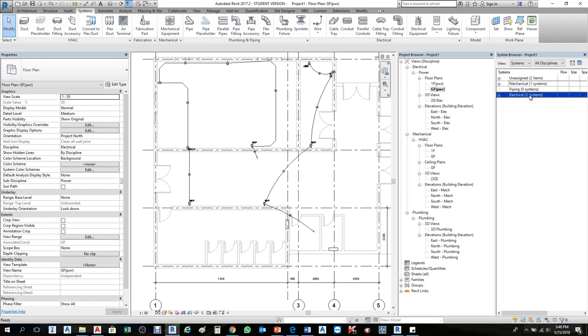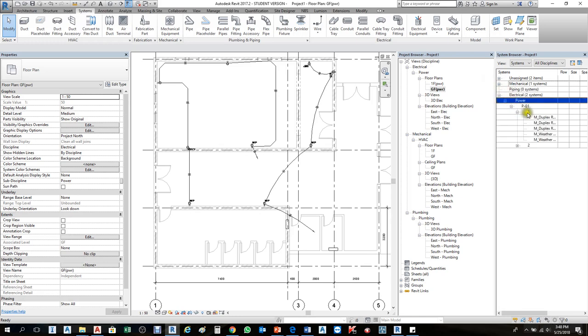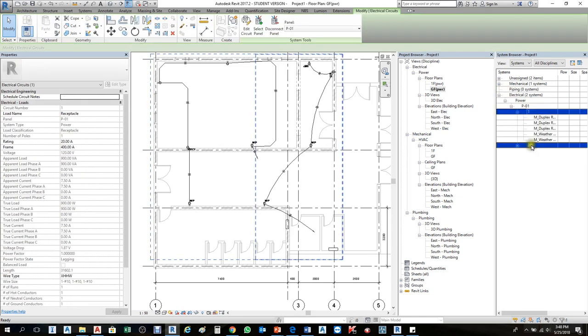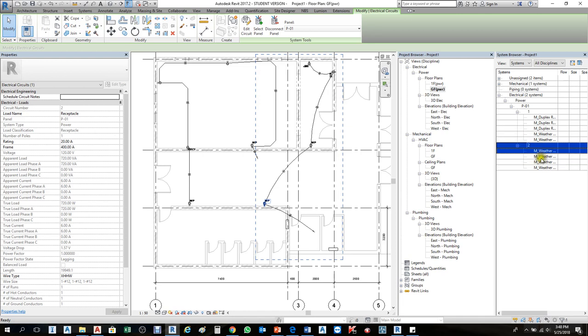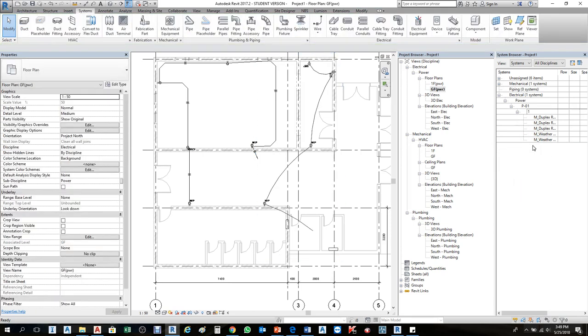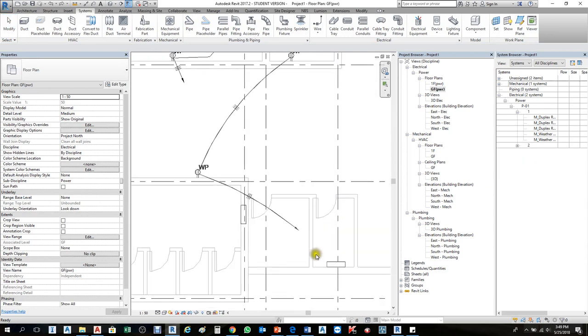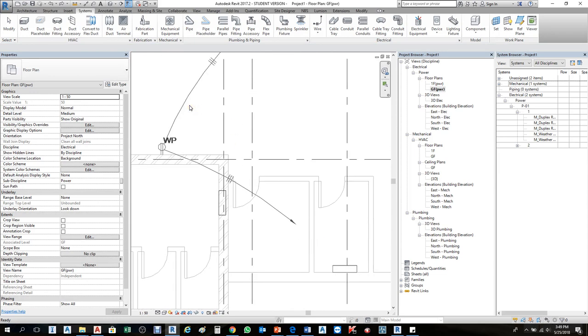Choose chamfer or arc wire type — I'll choose Arc Wire this time. Now these outlets all connect to the panel. Check the System Browser — under Electrical we now have two systems. Circuit one contains four outlets, circuit two contains approximately five outlets. If you want to delete a circuit, select it in the System Browser and delete — notice the wire symbol remains but the home-run arrow is removed, as that arrow is what defines the system connection to the panel.